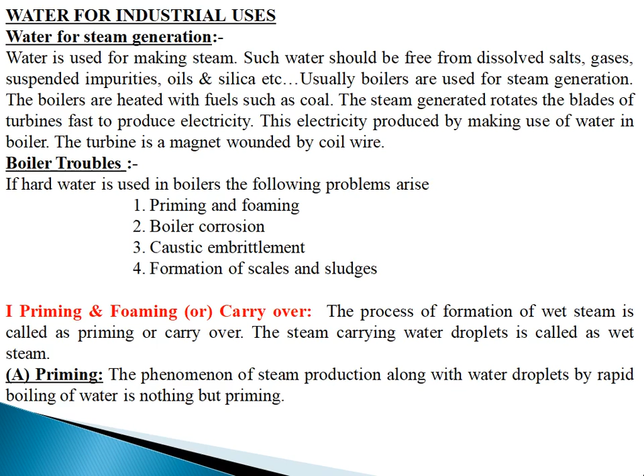The first problem is priming and foaming. When boiler water is boiling vigorously, some liquid droplets are carried along with steam, and these droplets carry some dissolved salts and suspended impurities. This is called carryover. Carryover occurs because of priming and foaming. There is a slight difference between priming and foaming. Priming means production of wet steam by rapid boiling of water in the boiler.